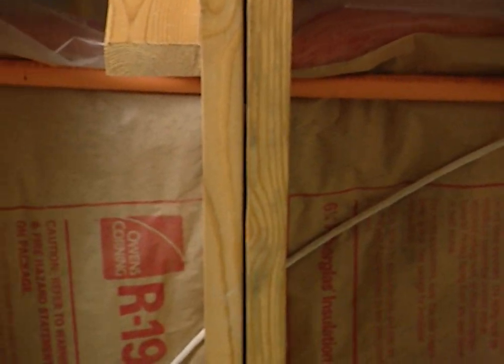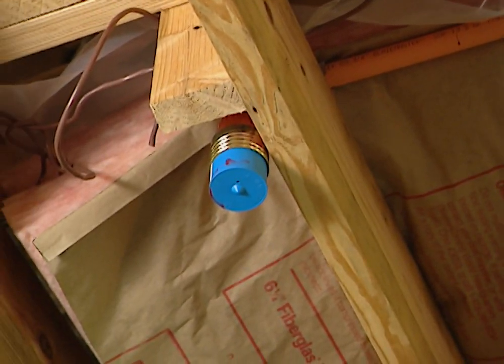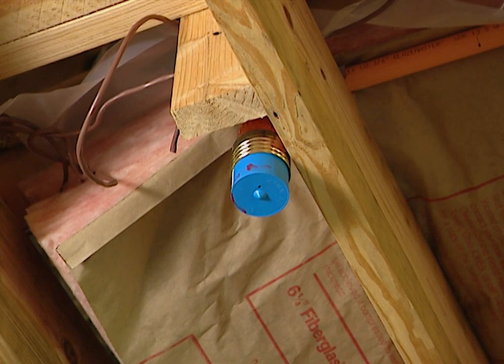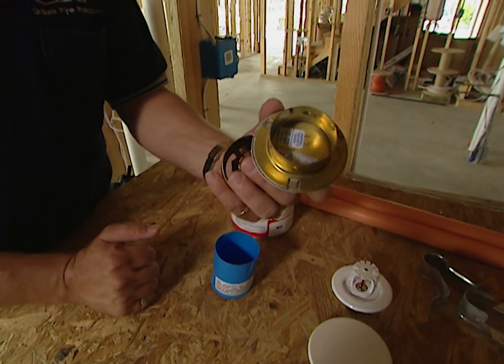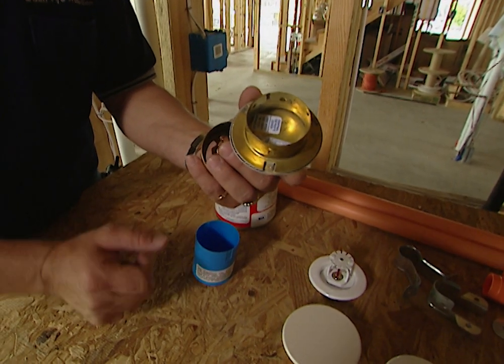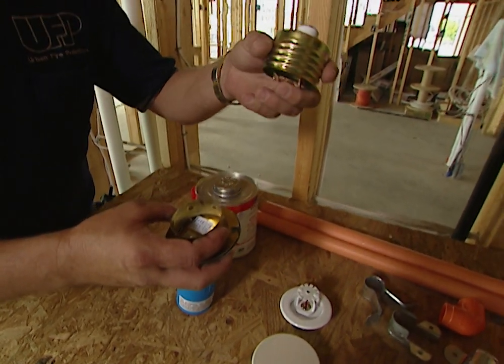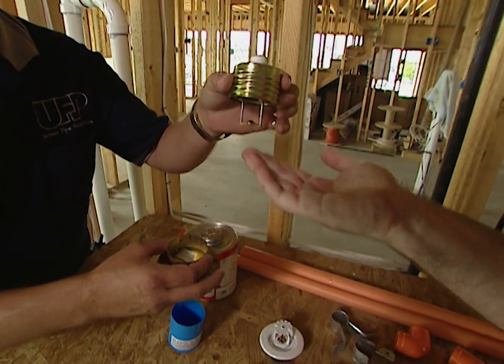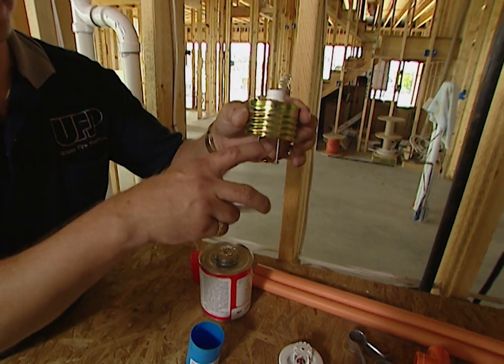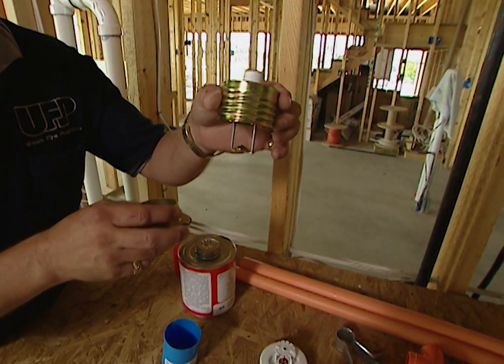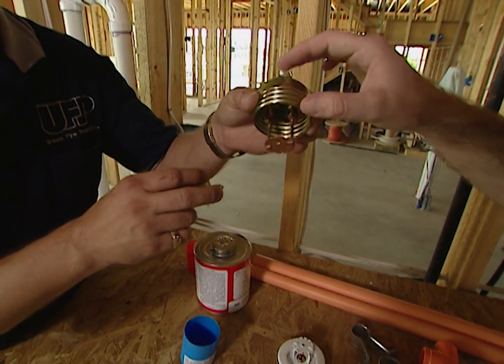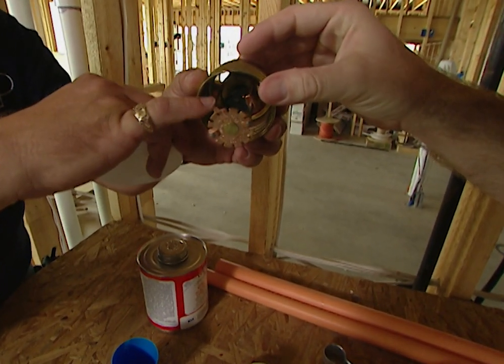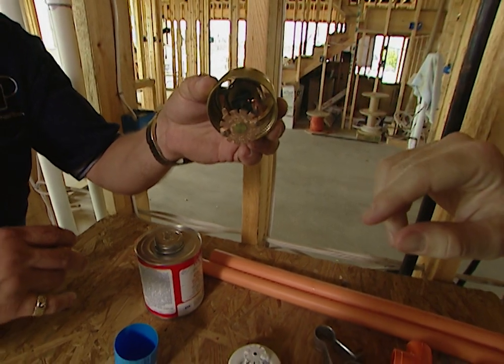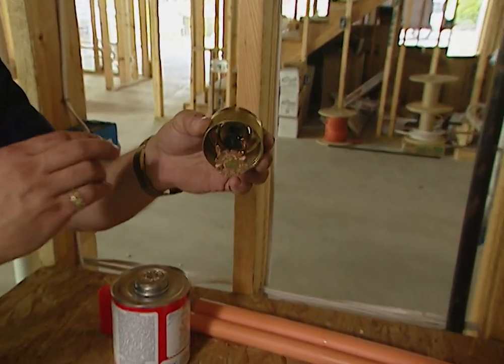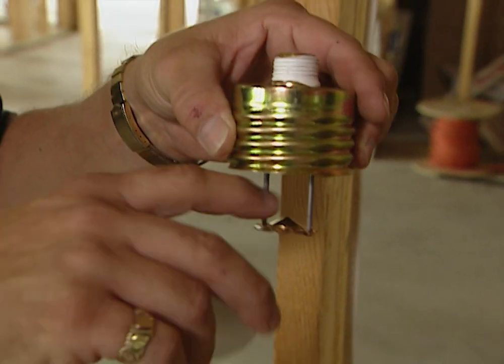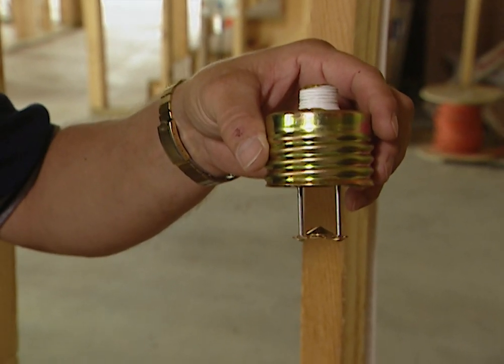The sprinklers are heat activated, so that only the sprinkler in the fire area actually activates. This solder that's in 3 points fuses at 135 degrees. The cover plate falls away, allowing the sprinkler deflector to drop. Just pops down, just a gravity fall. The deflector for the water falls at that point. It gets the sprinkler ready to discharge water. At 160 degrees, and you can see inside the fusible element there, that element softens, the water pressure blows it away, it hits the deflector and discharges in a spherical small droplet pattern.